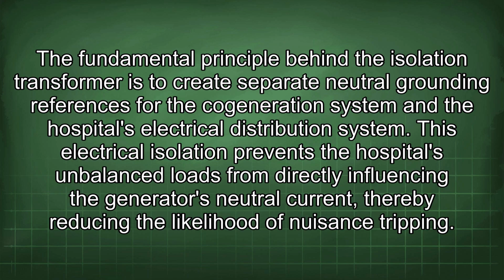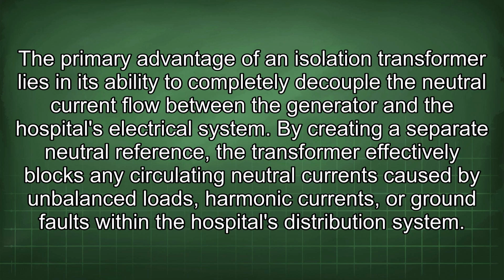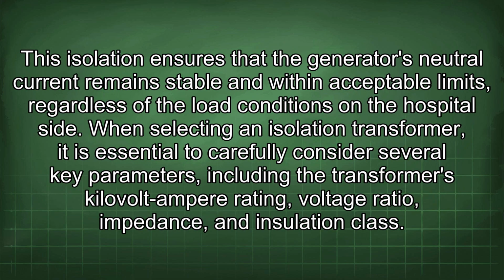This electrical isolation prevents the hospital's unbalanced loads from directly influencing the generator's neutral current, thereby reducing the likelihood of nuisance tripping. The primary advantage of an isolation transformer lies in its ability to completely decouple the neutral current flow between the generator and the hospital's electrical system. By creating a separate neutral reference, the transformer effectively blocks any circulating neutral currents caused by unbalanced loads, harmonic currents, or ground faults within the hospital's distribution system.